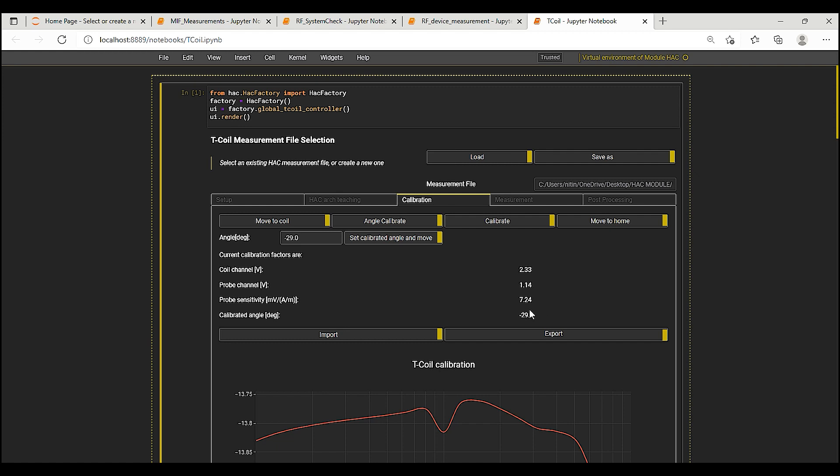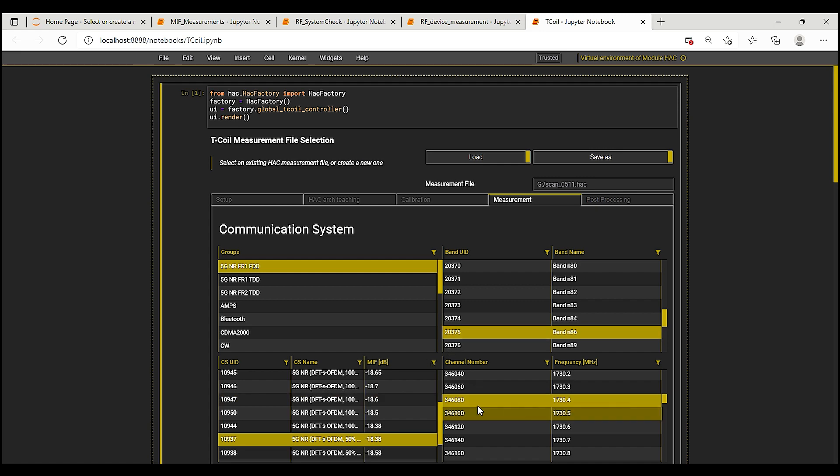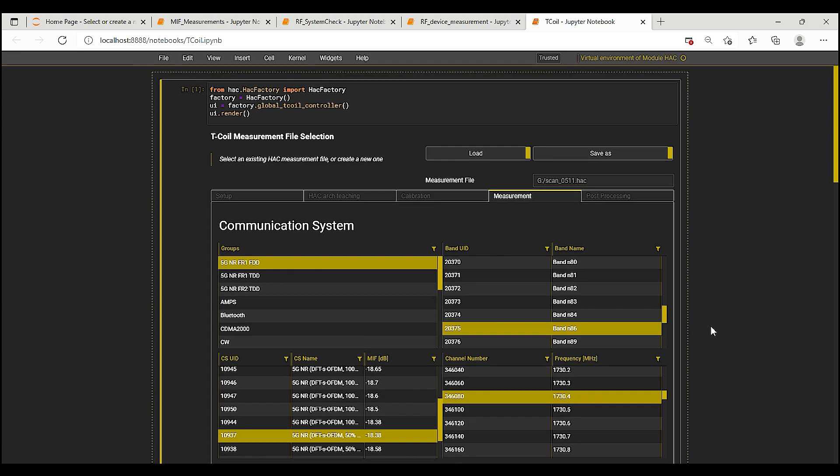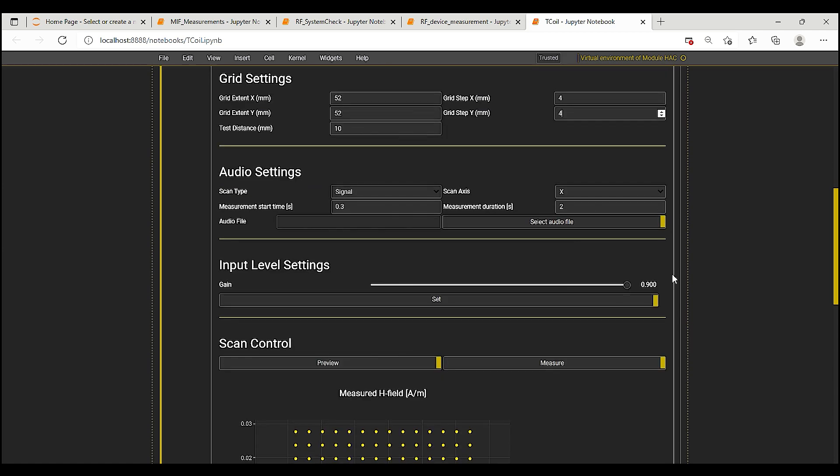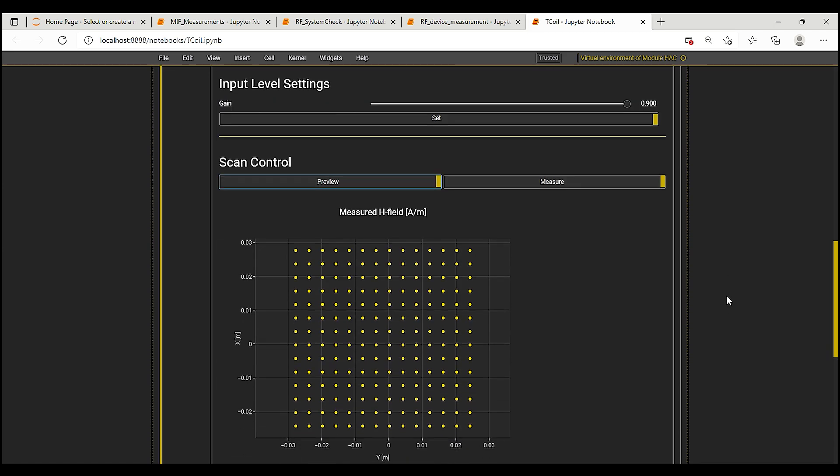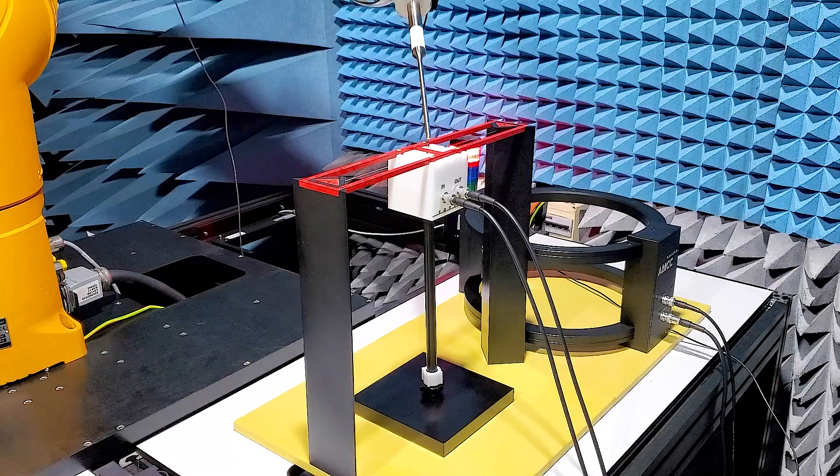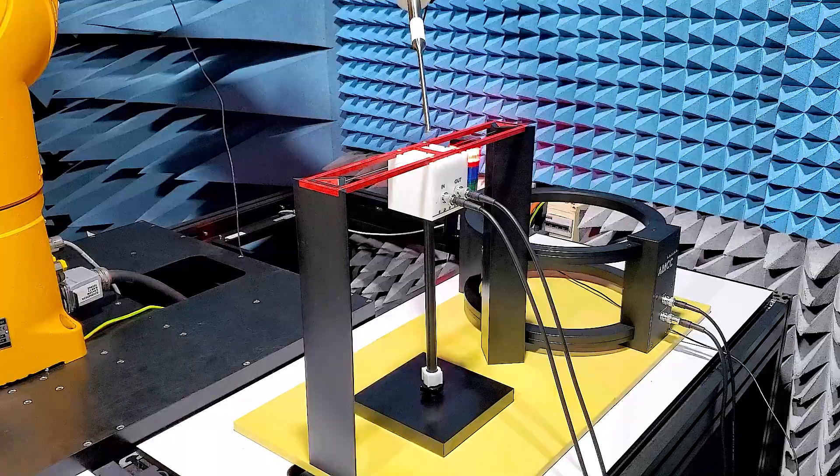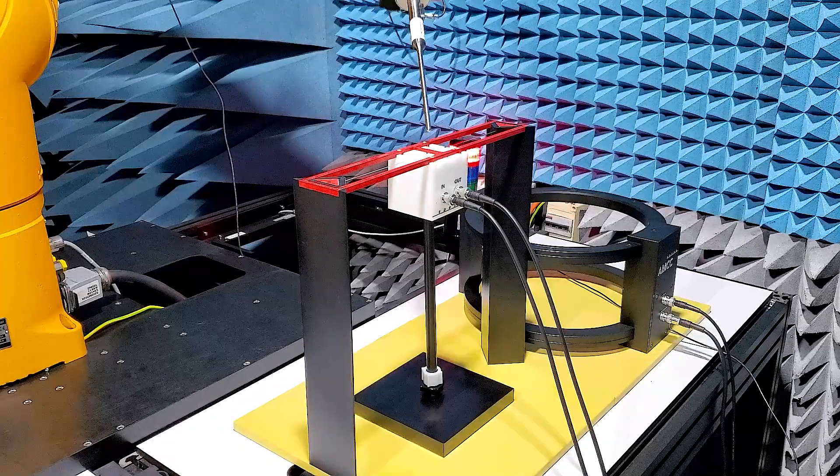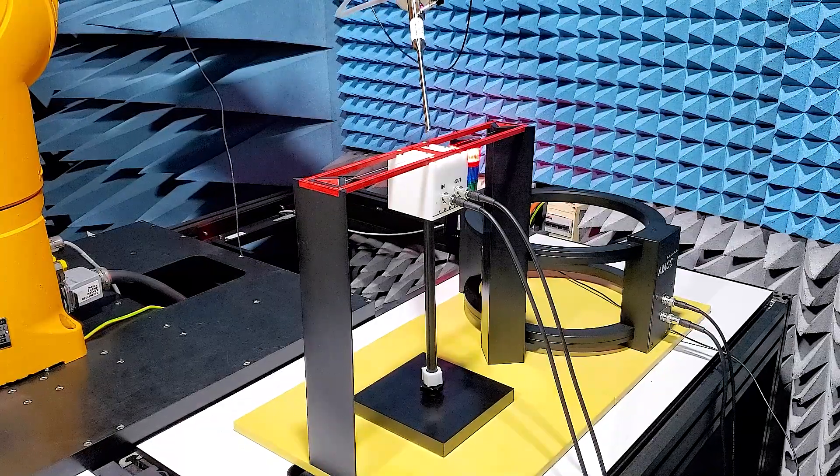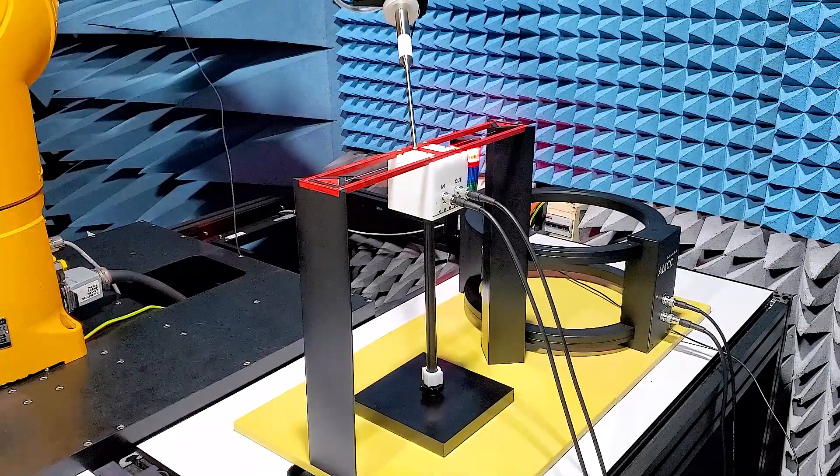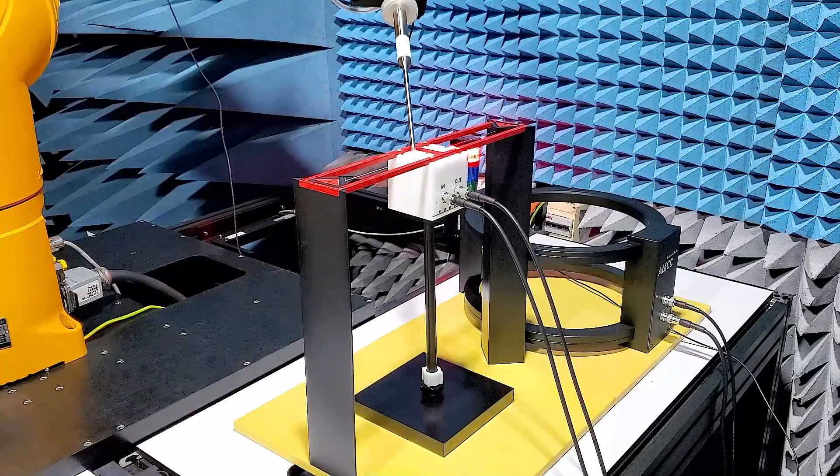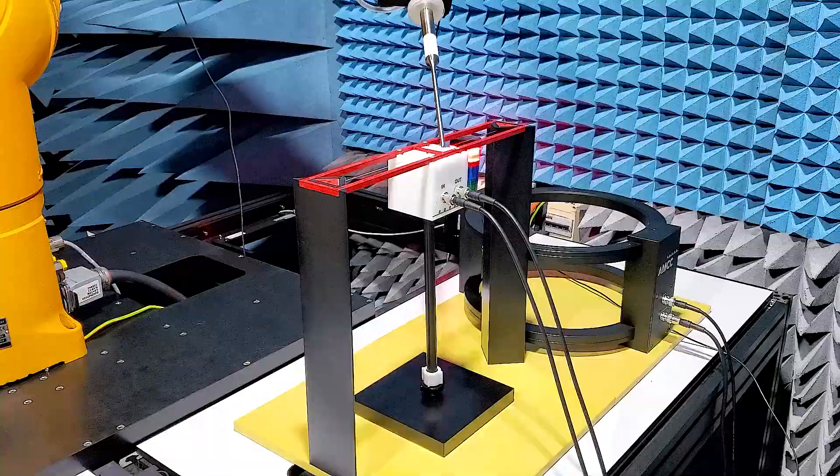In the Measurements tab, there are settings for the communication system, band and channel. I leave these unchanged as the TMFS is fed with an external signal and proceed to measure with the default grid which is in line with the standards requirements. The robot starts to measure the grid. The Measurements are done with the probe oriented in the south-west direction and the probe roll angle is set to the value determined in the previous step.